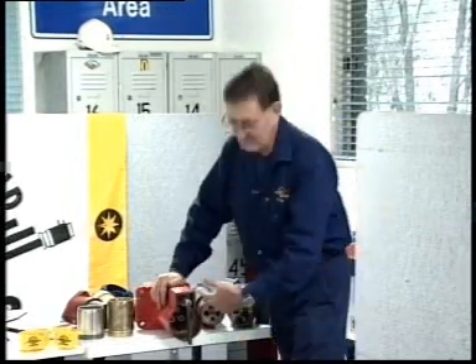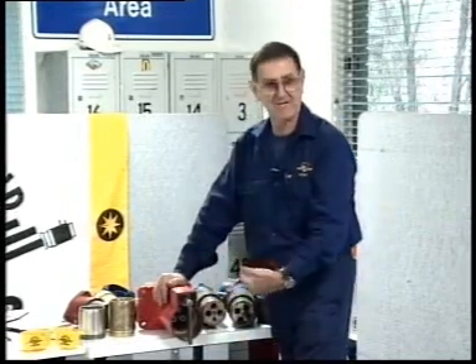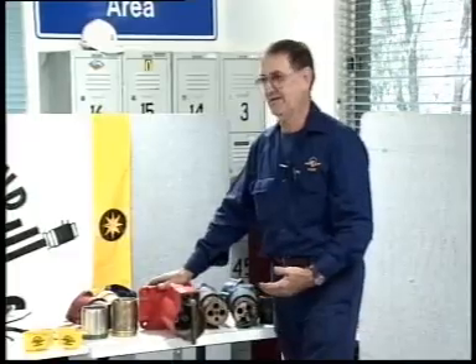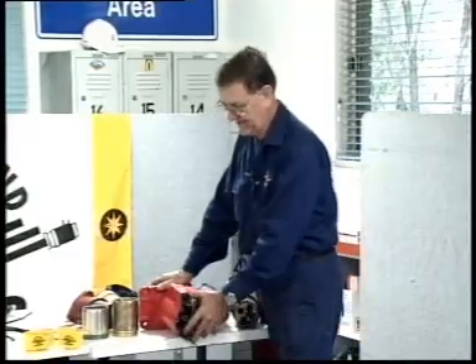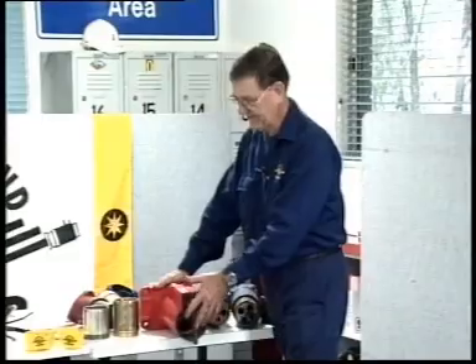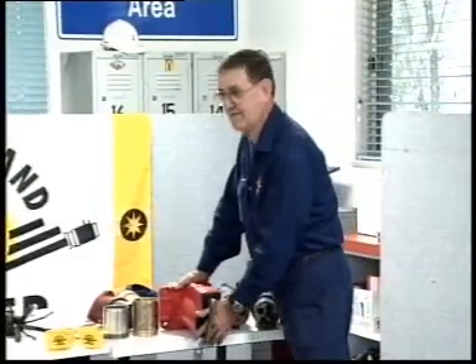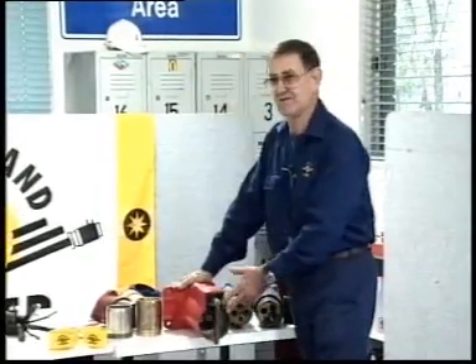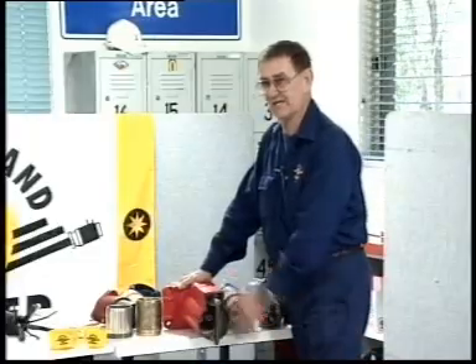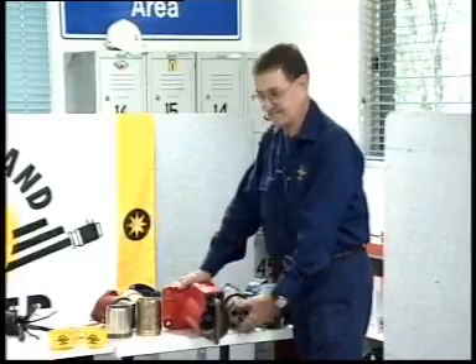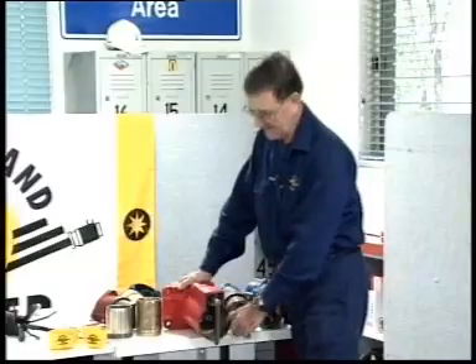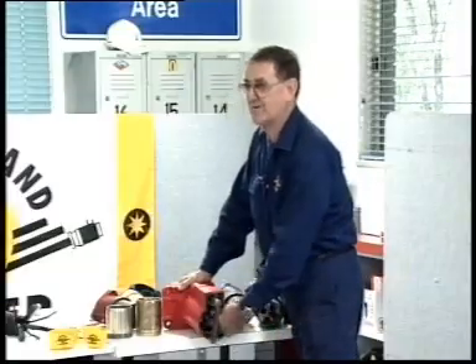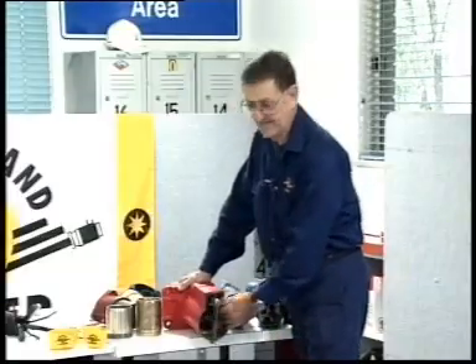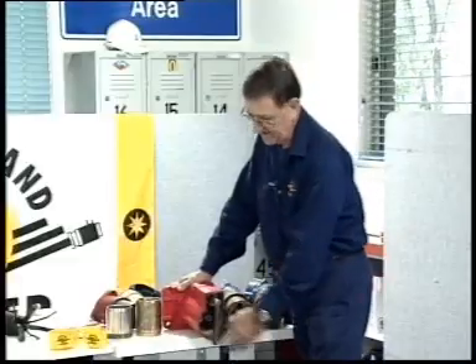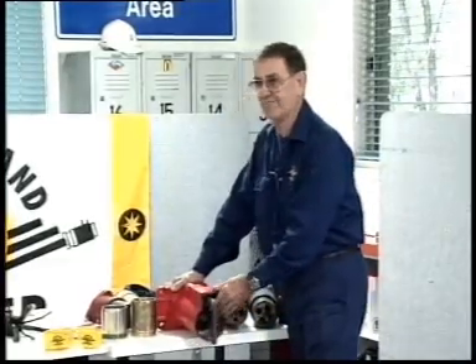Also, we have a look up there to make sure it's not full of gunk. It needs to be cleaned out. If you've got any of these underground that do not have a dummy plug in them, or an indicating plug, or they don't have some sort of cover in them, then they should have. Because if you don't, you're going to get moisture in there, you're going to get stone dust in there, you're going to get coal dust in there, you're going to have a problem. You're going to damage the flame path and create other problems with the contacts. So we need to make sure that's clean. So they should be closed up one way or another.